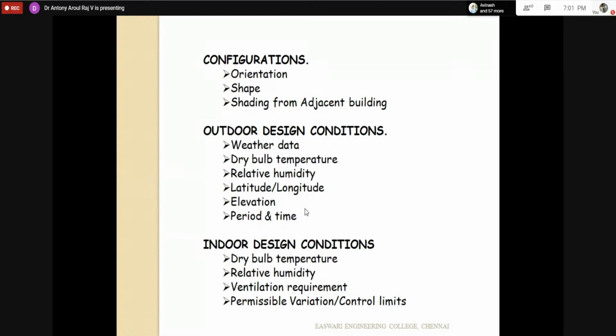So that is how we calculate. Also, the energy simulation or load calculation is dependent on the indoor design condition: indoor dry bulb temperature, indoor relative humidity, and ventilation requirement.